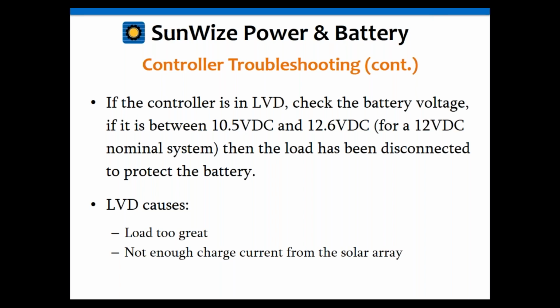So that means the system did what it was supposed to do and it was working the way it was supposed to be. So the system hasn't necessarily failed. It's just that it has failed to support the load. Now we have to find out why. And there might be multiple reasons why the LVD has occurred. The two main reasons are either the load was too big for the system or it's not getting enough charge current from the solar array.